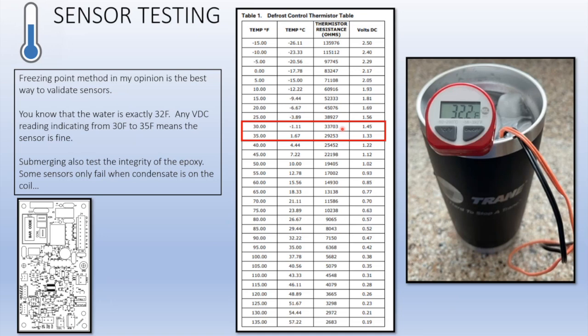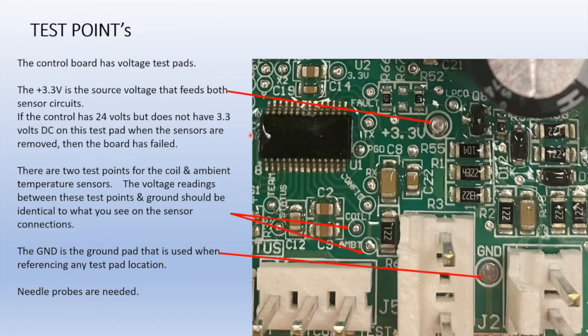With the exception that if one is at 35 and the other is at 30, then you may want to change one or both of them, because you want those sensors close to each other as well. Because it is a delta that triggers the defrost, and if you already have a delta or have a delta the opposite direction, then it may have to get colder in order to initiate a defrost. So each sensor needs to be between here, and I would say within a couple degrees of each other as well. And the test points for testing voltage.